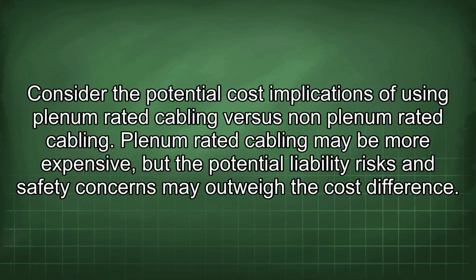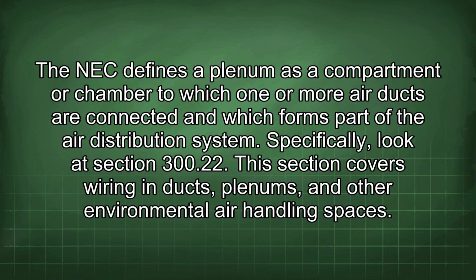Consider the potential cost implications of using plenum-rated cabling versus non-plenum-rated cabling. Plenum-rated cabling may be more expensive, but the potential liability risks and safety concerns may outweigh the cost difference. The NEC defines a plenum as a compartment or chamber to which one or more air ducts are connected and which forms part of the air distribution system.